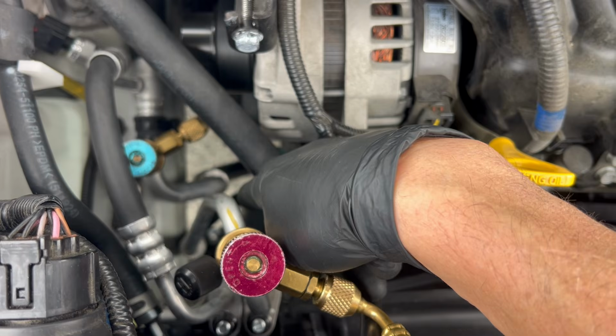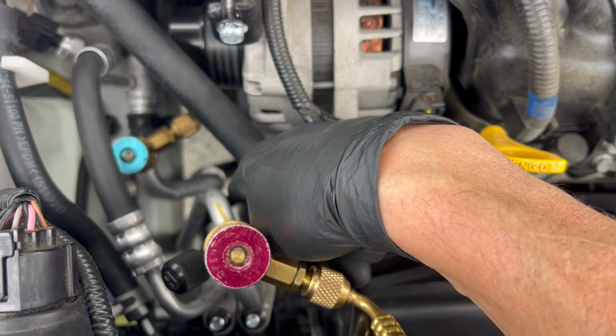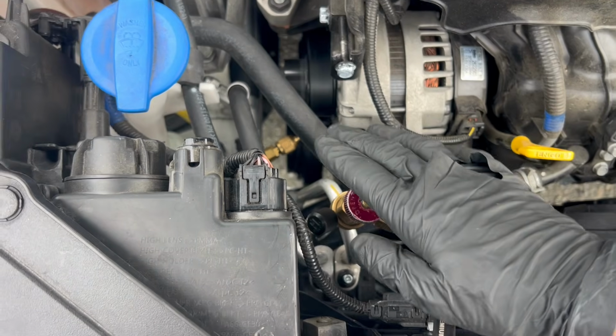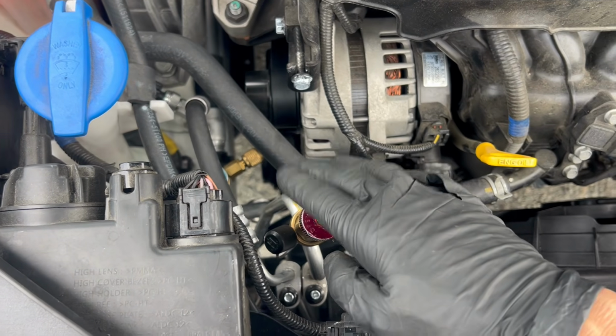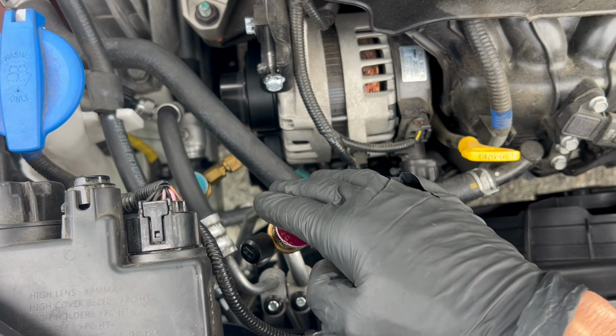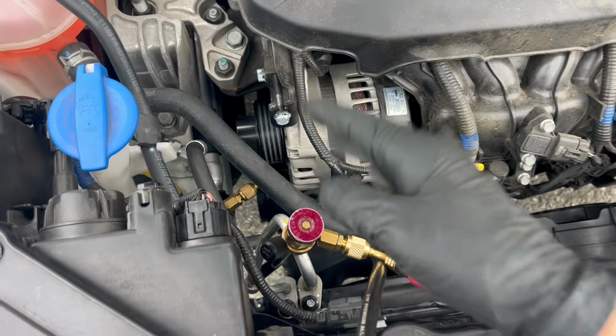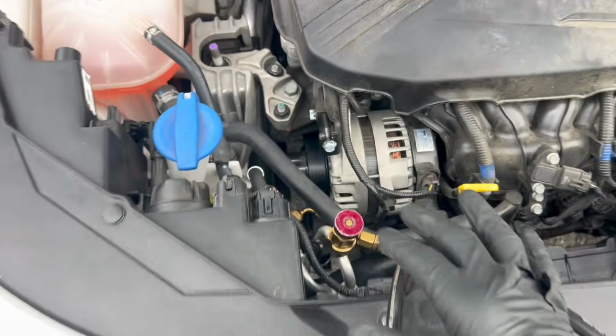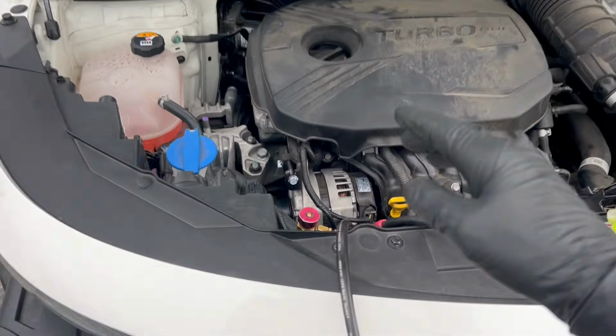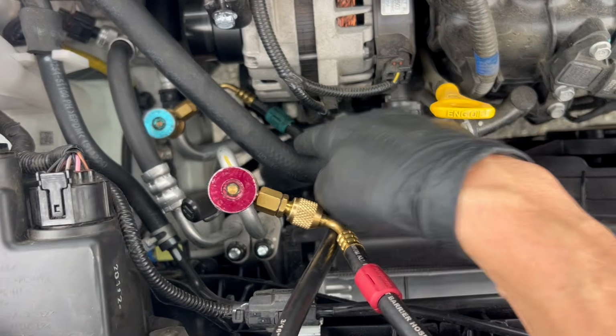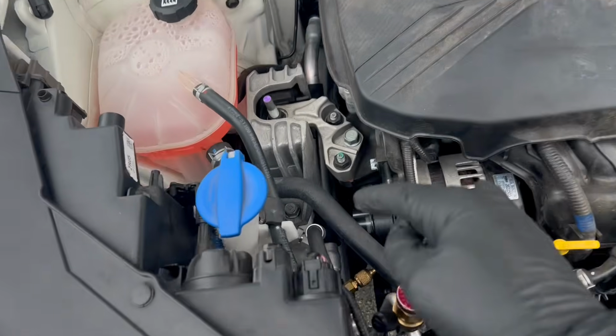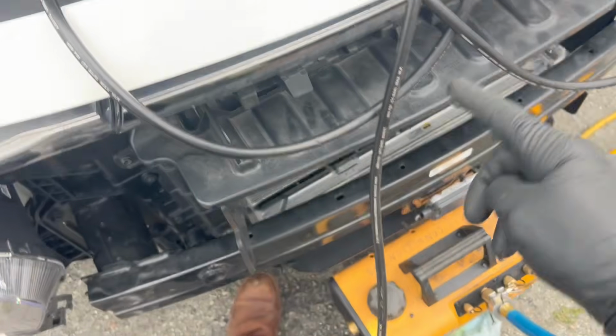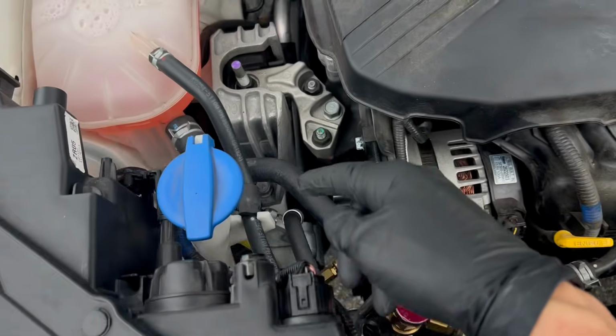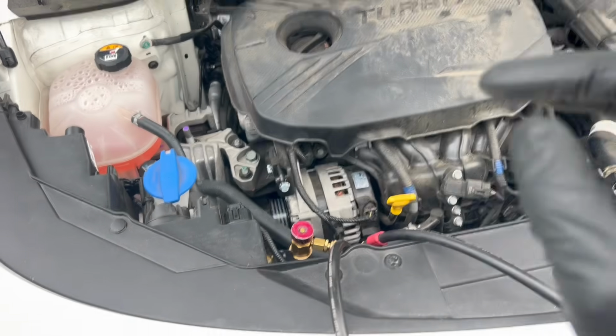Well, if the inner lining of that hose was collapsed a little bit, I would have an unusually low pressure right here. It may not be collapsed all the way. I still have some high side and you still have some cooling, but it would be unusually low right here, causing a cooling complaint. And then of course your transducer is on the other side of the condenser, so it'd be lower there. Now what you do is you take your temperature sensors, your clamp-on temperature.